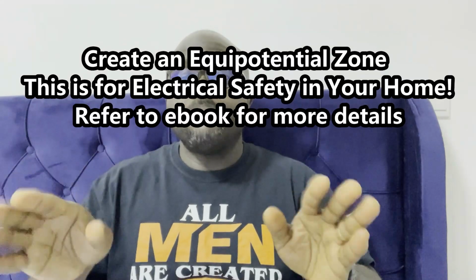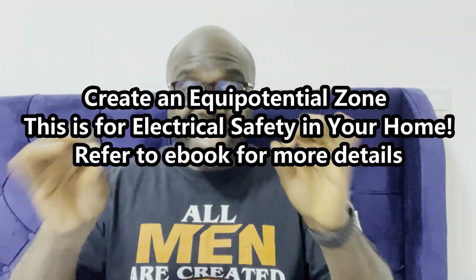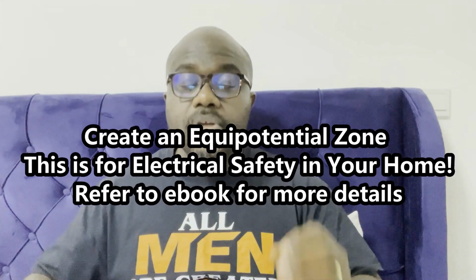Now we talked about bonding. Imagine if you're on the roof and you happen to have your hand on the structure while also in contact with a piece of metal on the roof. The structure rebars themselves need to be connected to earth, and the piece of metal you may be touching on the roof also needs to be connected to earth, so that everything is at the same potential. If not - if you're touching both at the same time and they're not at the same potential, and there's a faulty electrical incident - that's where current can come through your body and give you an electric shock.